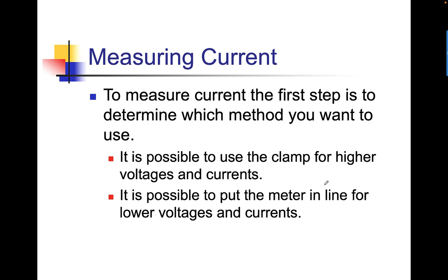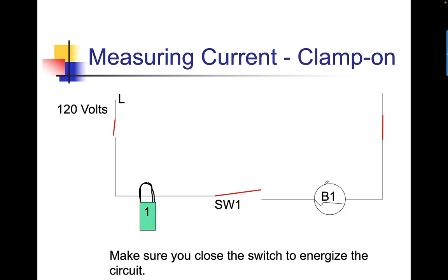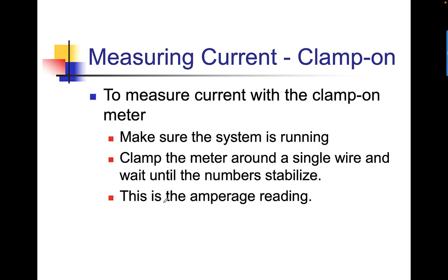To measure current, first determine which method you want to use. It's possible to use the clamp meter for higher voltages and currents, or to put the meter in line for low voltage and currents. 90% of the time you're going to use the clamp meter. Make sure you close the switch to energize the circuit. You'll clamp the meter across one wire — let me make this clear: one wire. You can't clamp across L1 and neutral or L1 and L2. As long as the circuit is operational, it's going to show a number. Clamp the meter around a single wire and wait until the number stabilizes — that's your amperage reading.